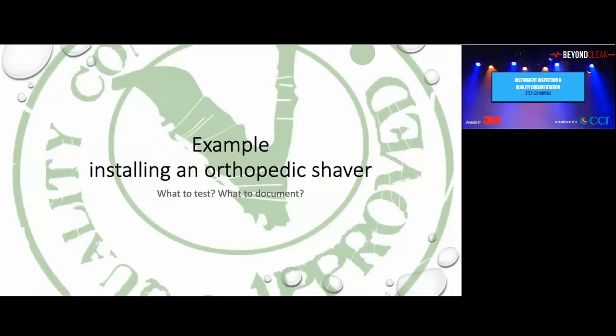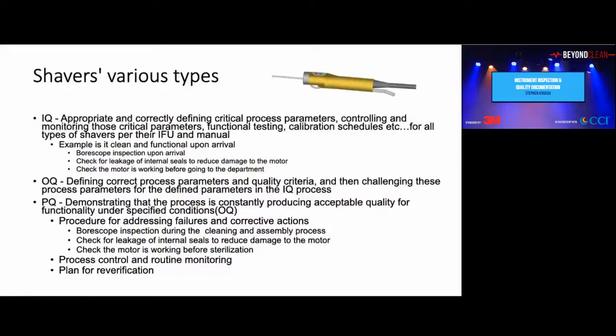So, installing an orthopedic shaver, what to test for and what to document. I broke this one out a little differently for you. Appropriate and correct defined critical parameters, controlling and monitoring those parameters. The example is clean and functional upon arrival. When you read that IFU, you've got to test it electrically and so on, but you also want to inspect it with a borescope. But you inspect it when it comes in. When do you inspect it? You should check for leakage and seals to the motor. You've got to plug it into a console to make sure it works.